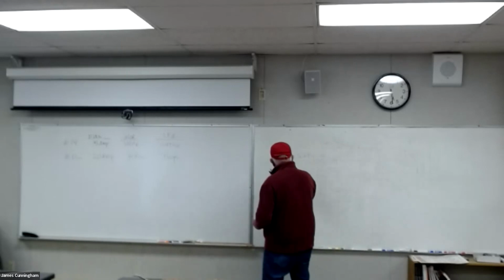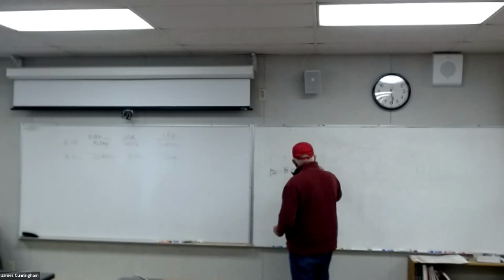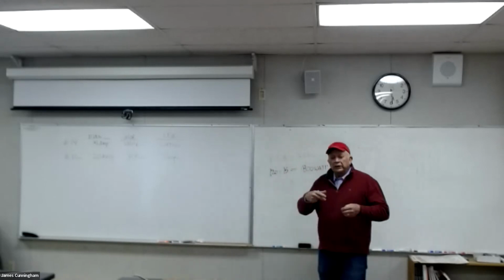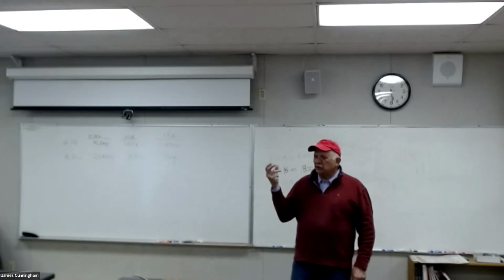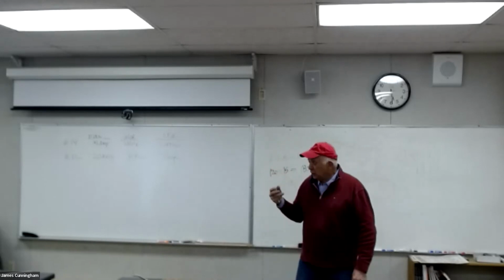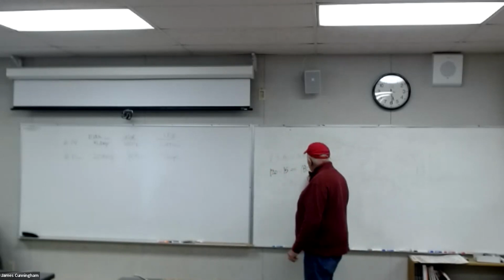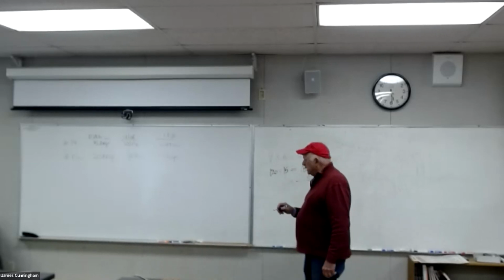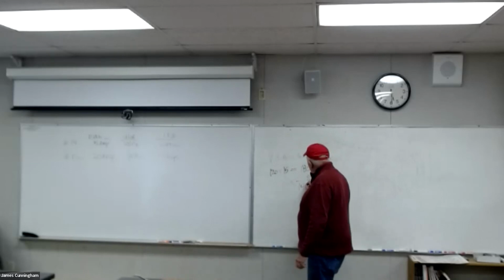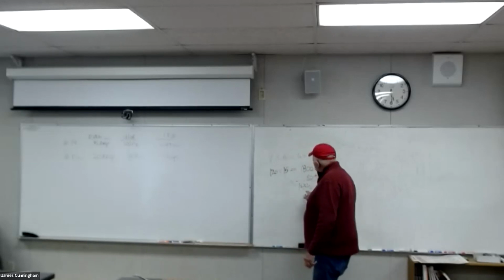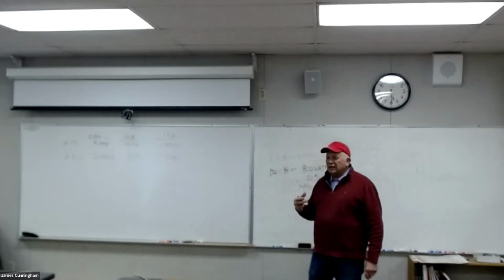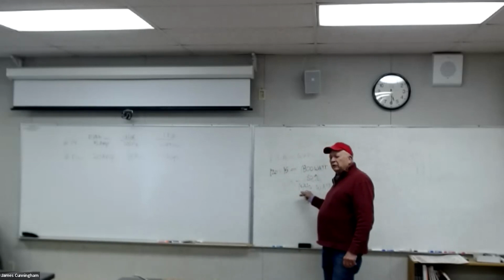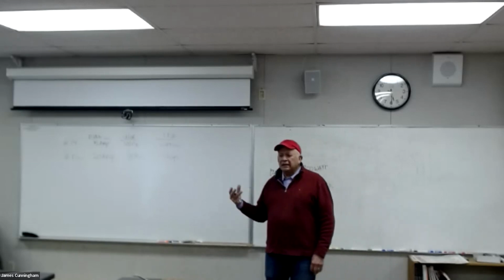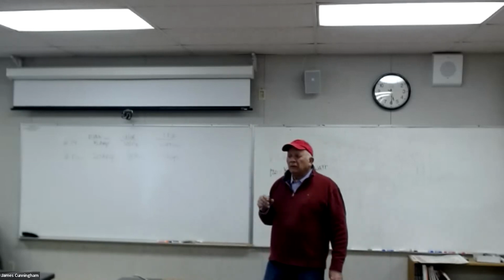Here we go. 120 times 15 gives me 1800 watts. According to the electrical code, they assume that each fixture is up to 150 watts if you have a light bulb. The other thing about the electrical code is they only allow you to use 80% of that. So 1800 times 80% equals 1440 watts. If I have 150 watts per fixture, I can't do any more than about 10 light outlets on a 15 amp circuit.